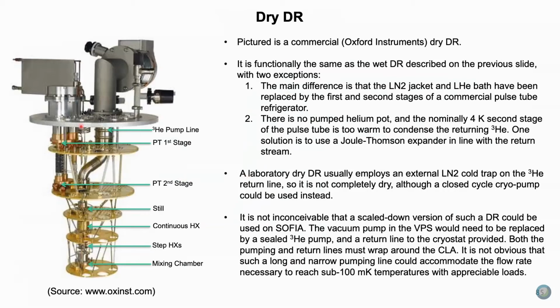This is similar, except it's a dry DR. So instead of a liquid nitrogen jacket with a liquid helium bath, we replace both of those with a two-stage pulse tube. So the first stage, which is here, cools this plate, which cools a large thermal radiation shield down around everything else. The second stage also cools a plate and another shield. And then down here, you've got the mixing chamber. This is the pumping line, which you can see is quite large. But this is for a very high capacity system.